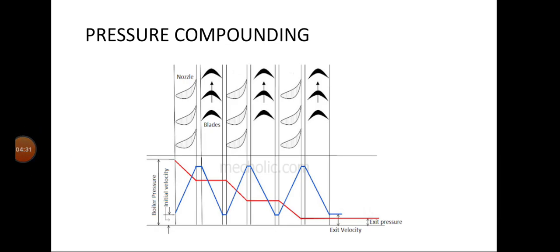In pressure compounding, it consists of a set of nozzles followed by a set of moving plates, then again a set of nozzles, moving plate, nozzle, moving plate — multiple stages of blades are mounted. The steam flows from left to right: it enters the nozzle, then the moving plate, then the nozzle again, then a set of moving plates. The velocity increases in the nozzle and decreases in the moving plate — this repeats continuously. The pressure drops in the nozzle and remains constant in the moving plate, and this cycle repeats at every stage of blades.